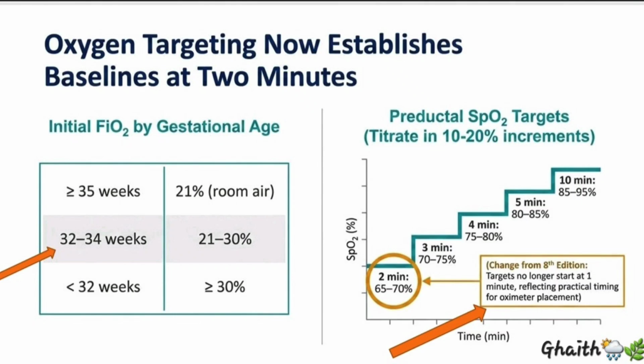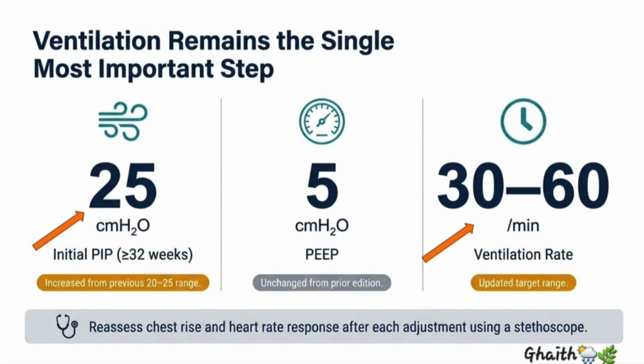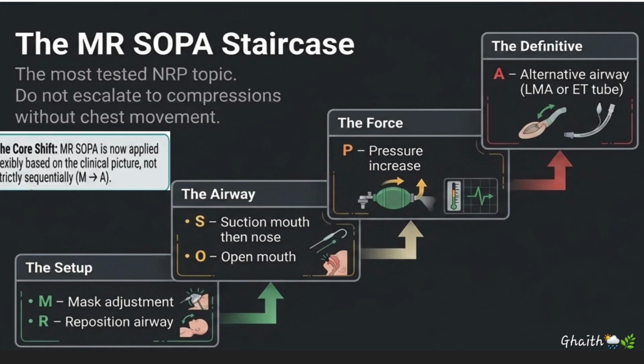For PPV settings, the initial PIP for babies 32 weeks and older has increased to 25 centimeters of water. For those under 32 weeks, use 20 to 25. PEEP should be 5 centimeters of water, and the ventilation rate is 30 to 60 breaths per minute. If positive pressure ventilation does not result in chest movement, you must troubleshoot using MR SOPA.